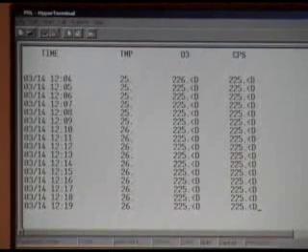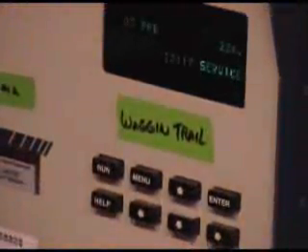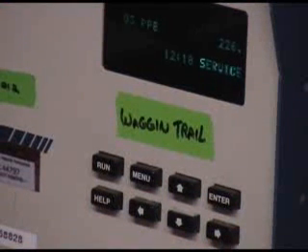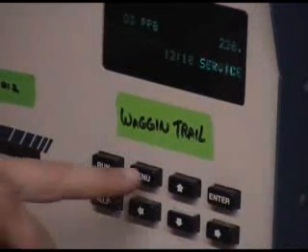As you can see, our cal has held really good. It's about flat, solid, nice and straight, level, no bumps, no nothing. Looking great. We're going to start taking readings about 12:20, and we're going to place our analyzer back in remote mode because we're not going to make any changes to this calibration.